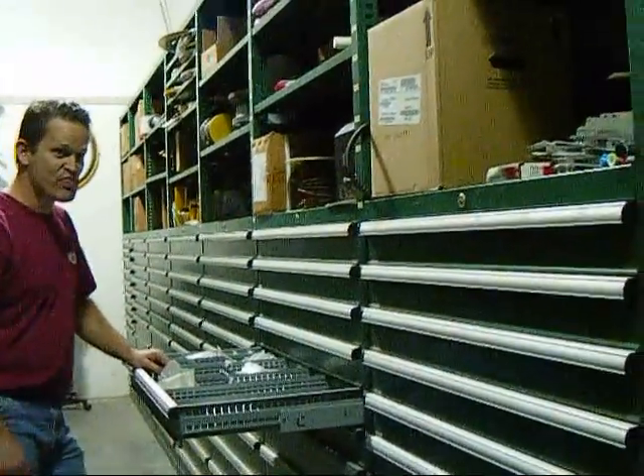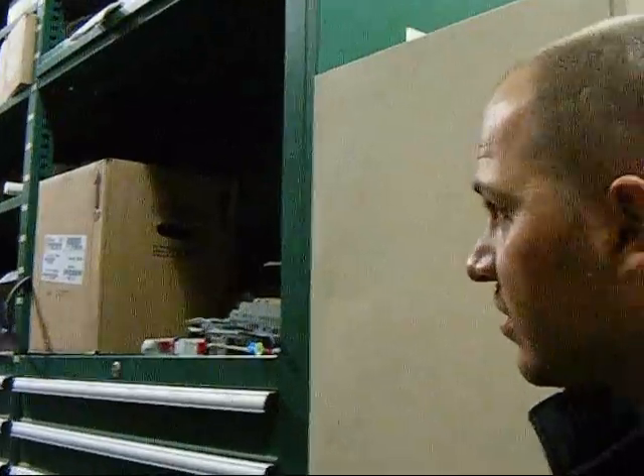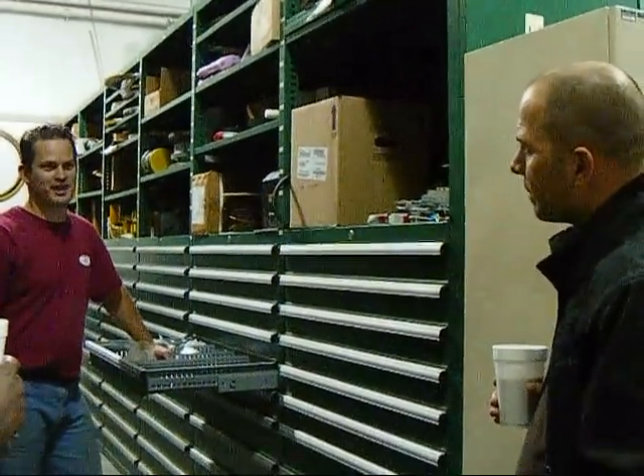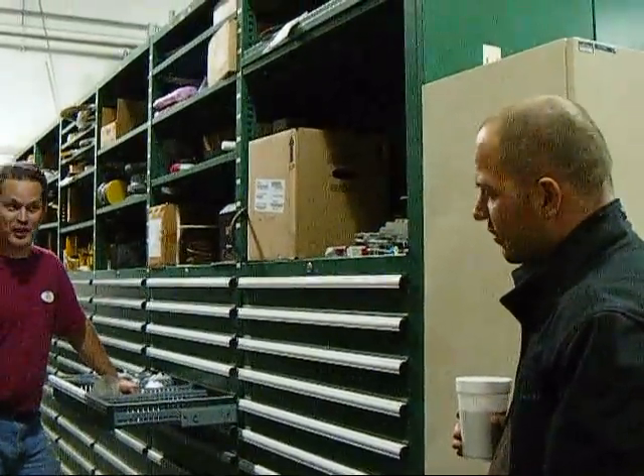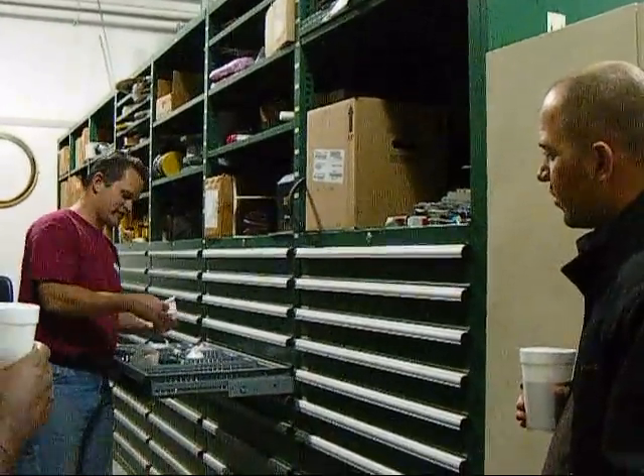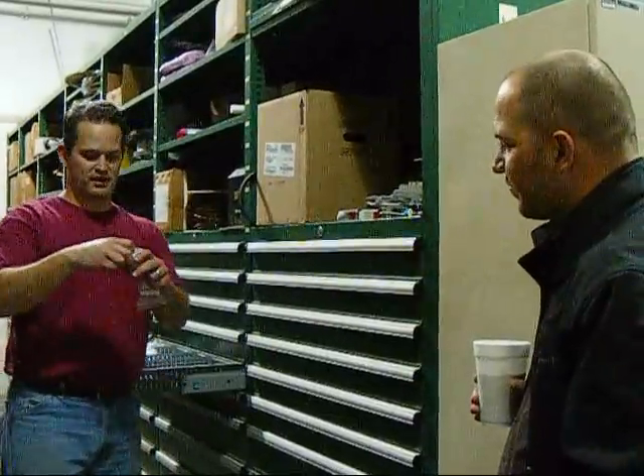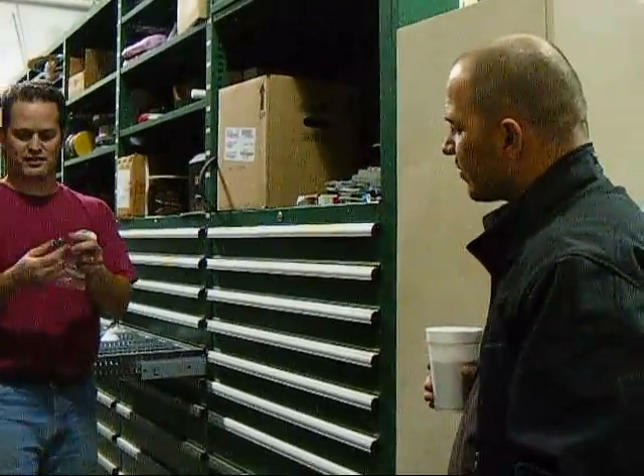Actually, the plugs for the weights are already set. The eccentricity is set. There's a hole that you put your weight in already. I've got pictures of those — we call them balance planes. They're the holes that we screw these into. We drop these balance weights in and then screw this plug down, and that plug locks the balance weight in.